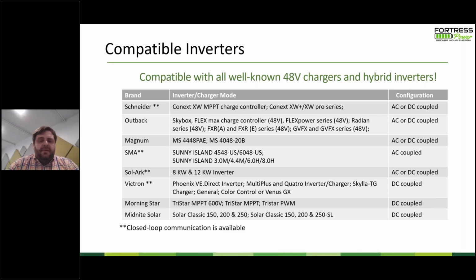So Schneider, SMA, and Sol-Ark, that's the Sunny Island series for SMA, we have closed loop support with. The other battery inverter manufacturers, there's a lot of Outback fans out there. Outback has great quality, same with Magnum and Victron. You would just operate the battery in voltage-based control, and that is less of an issue in terms of usability.